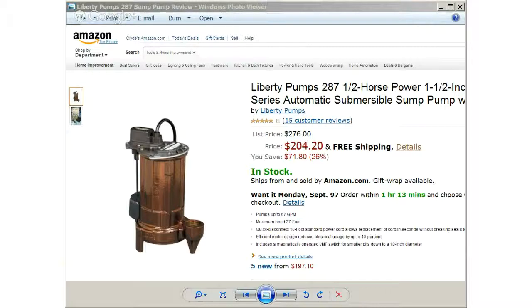All fasteners are corrosion resistant stainless steel. The Liberty Pumps 287 1/2 horsepower is a 3450 RPM motor. Discharge is 1.5 inch with a powder coat finish, 115 volts, 8.5 amps AC motor.